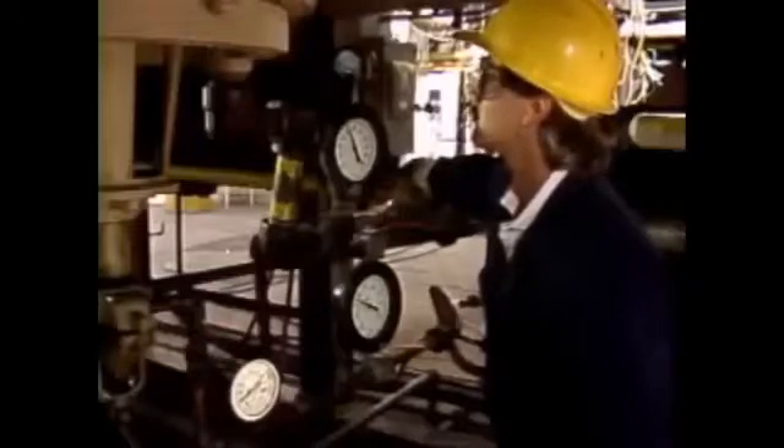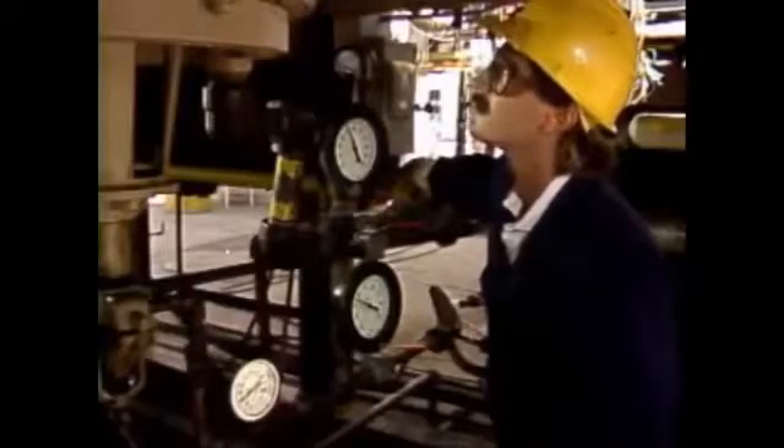To do this, we'll assume that the pilots have already been lit, but that the burner fuel valves are still closed. You may recall that oil burners have atomizers, or oil guns, that break the fuel oil into a mist so it will burn easier. This burner has a steam atomizer. The first step in putting it into service is that the operator opens steam valves to get steam flowing to the atomizer.